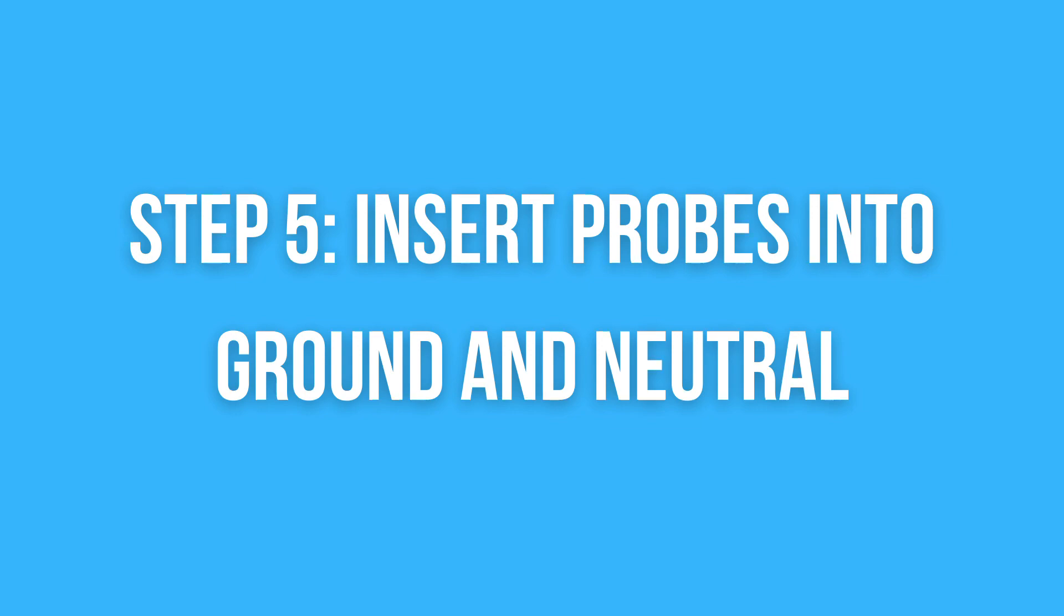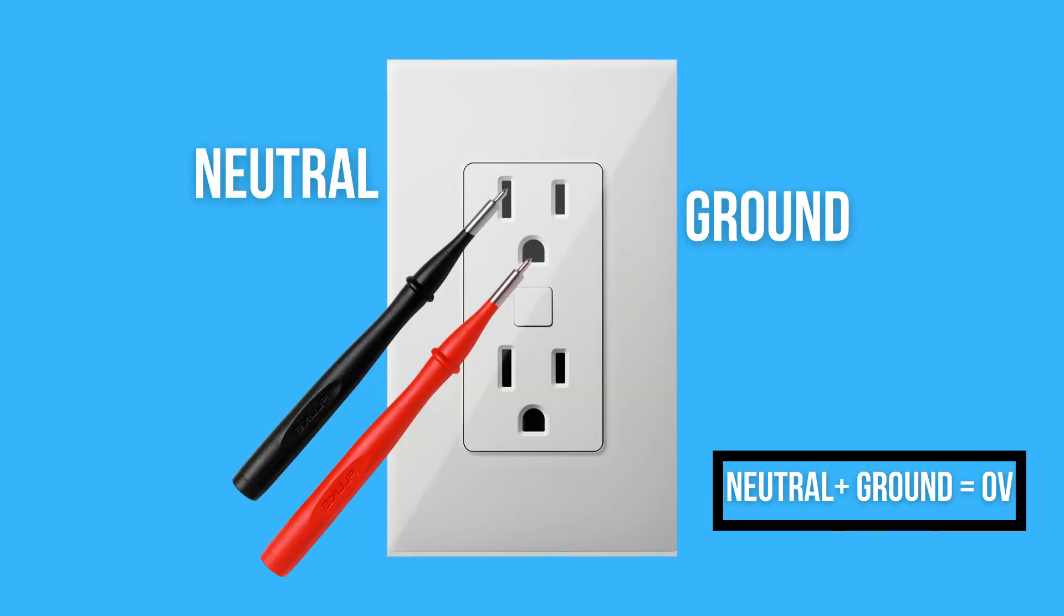In the last test, you should connect the probes with neutral and ground holes. The result of this measurement should always be zero. If the multimeter shows a voltage higher than zero, it means that the hot wire is touching one of these two wires, and it would be best if you fix that right away.